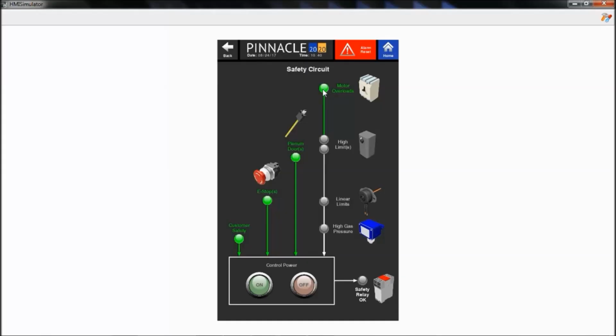So I see that my motor overloads are responding with a positive signal, but my first high limit switch isn't. If we go ahead and look at the high limit, we see that it has in fact been tripped. So we push the reset button on the high limit switch, and we'll see that everything else below it lights up, and we can then start our control power.